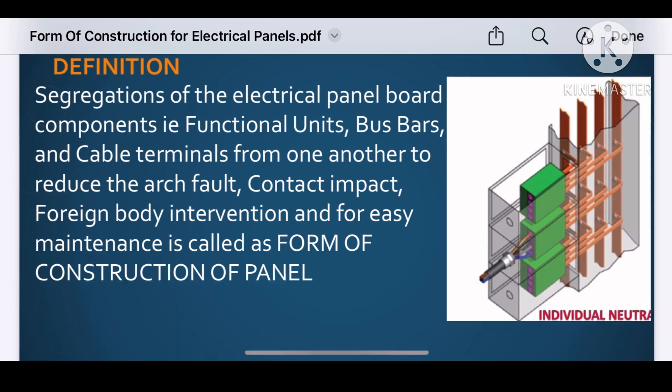Let us understand the definition. The definition says that the segregation of the electrical panel board components — like functional unit, bus bar and cable termination — from one another, in order to reduce arc fault, contact impact, foreign body intervention, and for easy maintenance, is called the form of construction of panel.